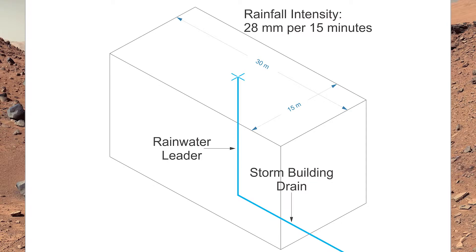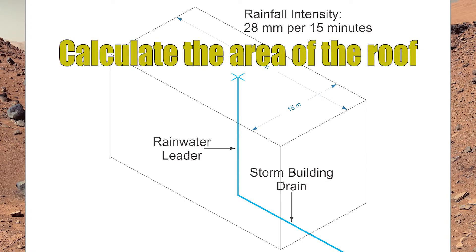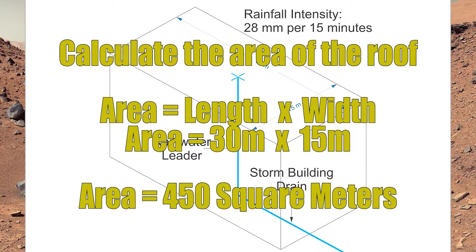We find the rainfall intensity value in the National Building Code. I have a building here with one flow control roof drain right in the middle. The building has a roof that is 30 meters by 15 meters. I have a vertical pipe going straight up and down in the middle of the building — that is called a rainwater leader — and when it turns the corner and goes horizontal, we call that the storm building drain. The area of this roof is simply length times width: 30 meters times 15 meters equals 450 square meters.